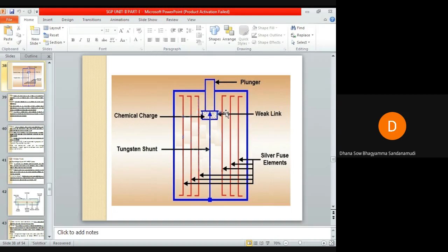So let us discuss in detail. The body of the fuse is of ceramic material with a metallic cap rigidly fixed at each end. A metallic cap is fixed at both ends, at the lower end and at the upper end. These are connected to a number of silver fuse elements. Of course, here you can see only a few silver fuse elements. They can be more than that. At one end is a plunger which under fault condition hits the tripping mechanism of the circuit breaker and causes it to operate. The plunger is electrically connected through a fusible link, chemical charge, and a tungsten wire to the other end of the cap. You can see here there is a plunger which is electrically connected through a fusible link, chemical charge, and tungsten wire to the other end of the cap. This is the other end of the cap.